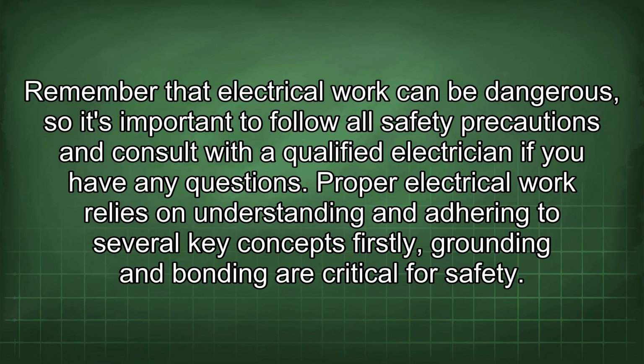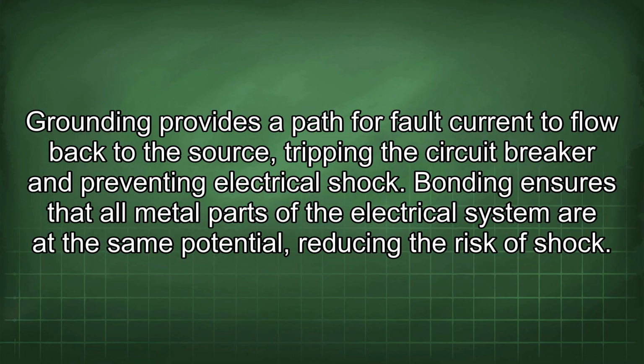Proper electrical work relies on understanding and adhering to several key concepts. Firstly, grounding and bonding are critical for safety. Grounding provides a path for fault current to flow back to the source, tripping the circuit breaker and preventing electrical shock. Bonding ensures that all metal parts of the electrical system are at the same potential, reducing the risk of shock.